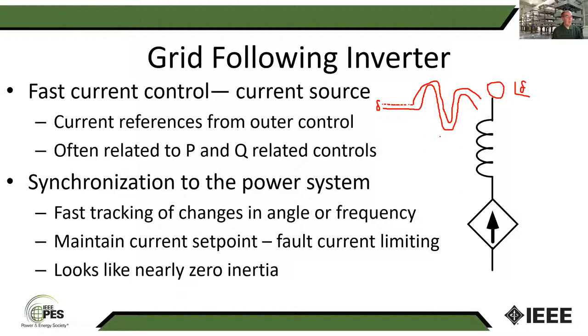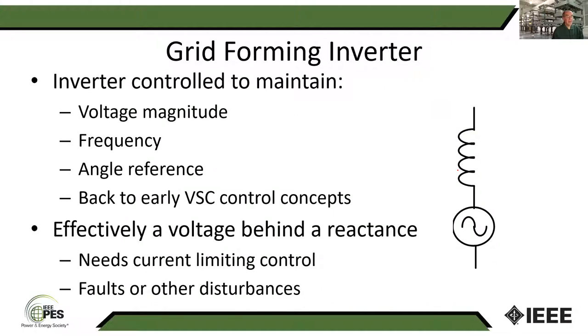So if you look at that case I had earlier where I had the two hydro machines and then photovoltaics that were connected to the system, we had those all lumped at one bus, but they were actually going to be spread out. You had those synchronous generators that you could view as the masters that are going to be setting things for the system. If you have a microgrid that has all inverters, you can't have all grid following inverters. You're never going to have any frequency control in the system, and everyone's going to fight each other.